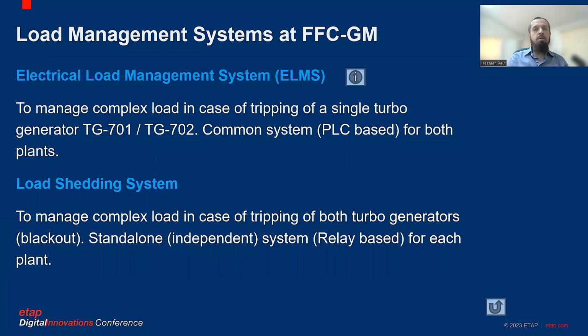The second system we call the load shedding system. It is a relay-based system, independent for each plant. It is just to ensure safe shutdown of each plant whenever there is a blackout, that is, both turbo generators are tripped. So this phase of the project covered only the replacement of the electrical load management system, ELMS. But in the second phase, we also plan to merge the load shedding system of plant 1 with the upgraded ELMS, so as to have a common system for load management at plant 1.